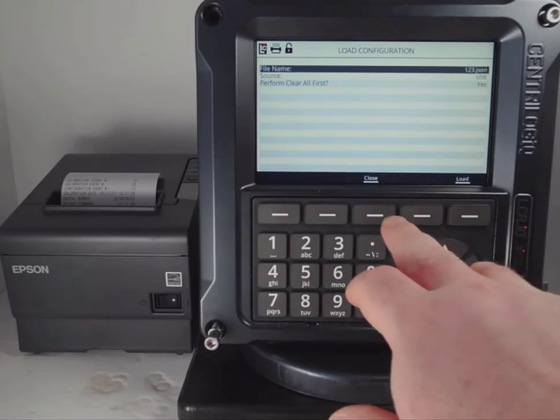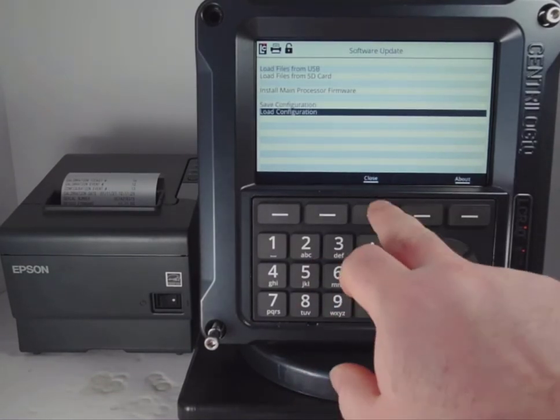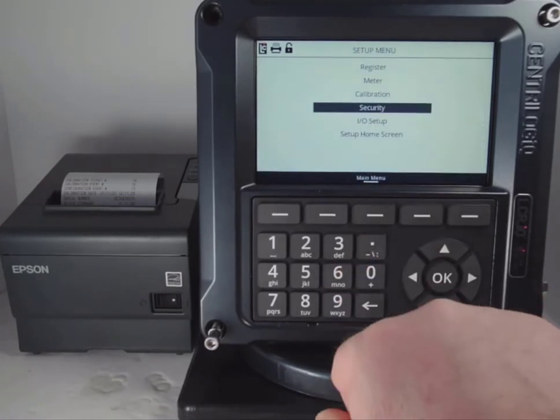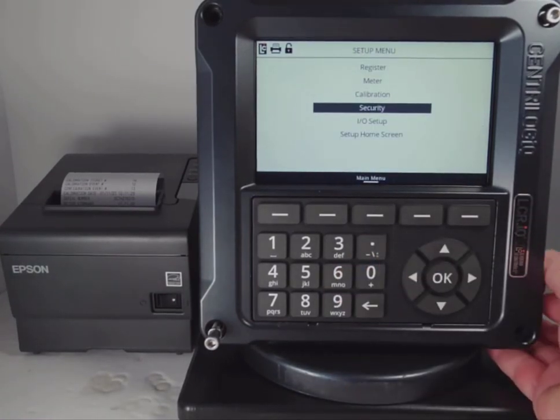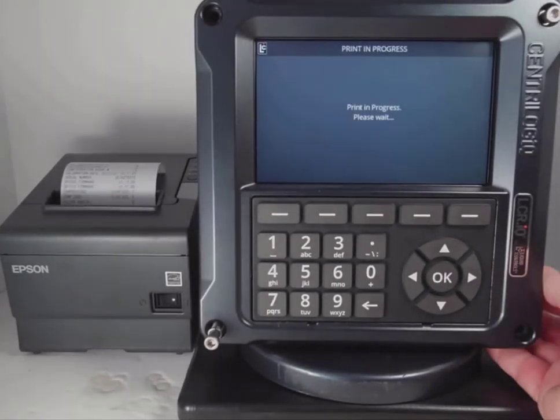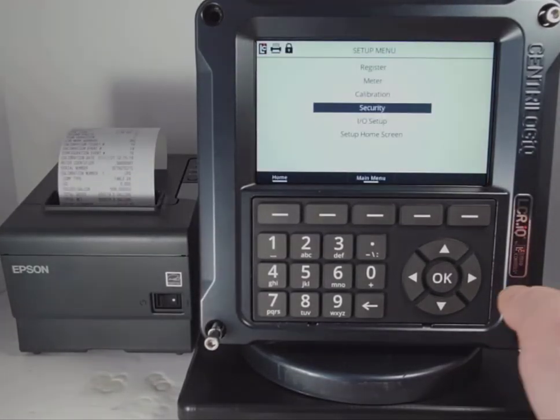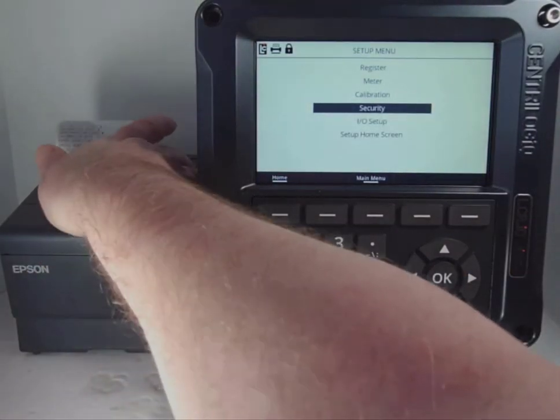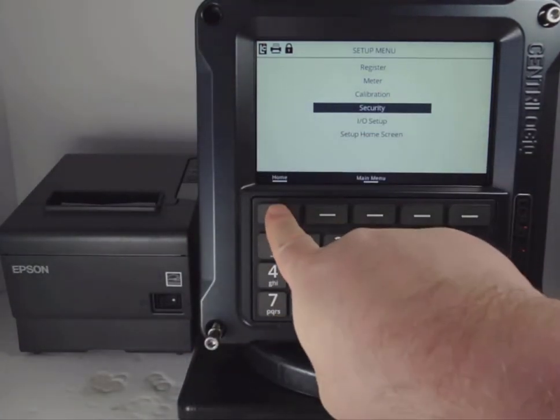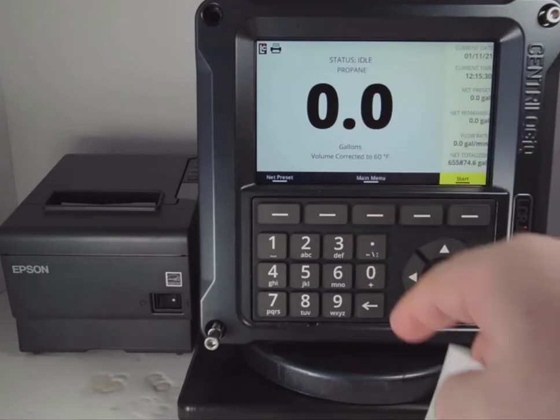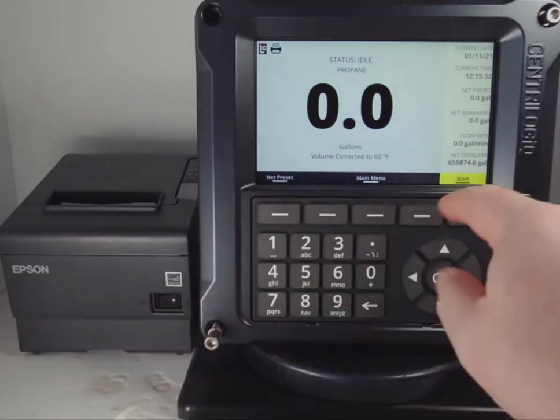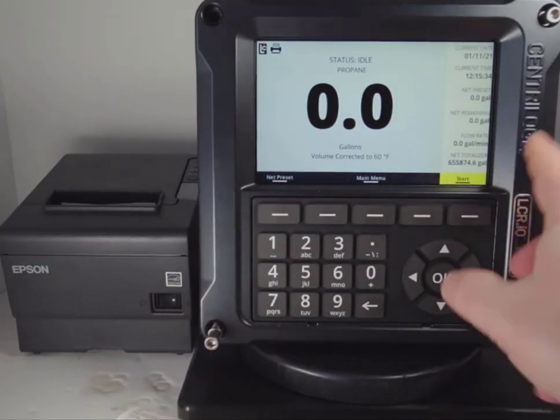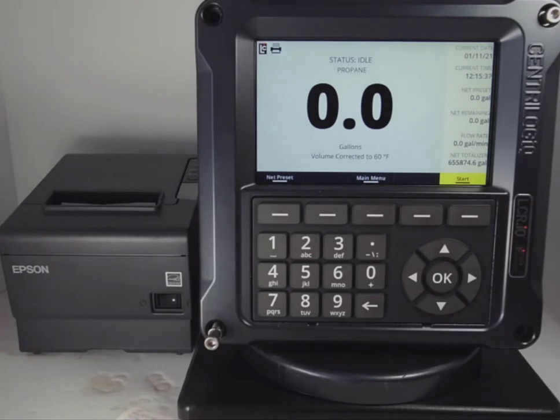Now my configuration is saved. If I press the close button, you'll see, if I go all the way back and put the register out of the calibration position, when I print my calibration ticket, all my information is up to date. When I press the home button, my product information and everything I had in there previously, my time, date, and totalizer information, is all back intact since I had downloaded that configuration.